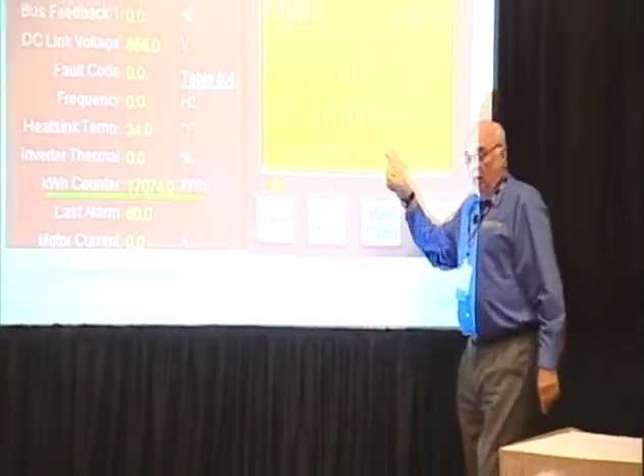Here we have a VFD, and I'm coming back to the real-time energy monitoring. So, in the automation system, we see the kilowatt-hour counter, and that's the same value, kilowatt-hours, off the speed drive. Okay, so we can now, and I'll show you next, add up all the energy consumption of the chiller plant via BACnet. So, here we have the chiller power, pump power, cooling tower pump power. We know the total tonnage. So we now have real-time kW per ton. Now, the condenser pumps are constant speed devices, so we calculate a kilowatt-hour value from the amps that are read by the current transducer.